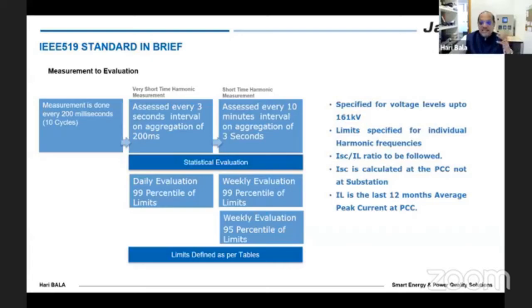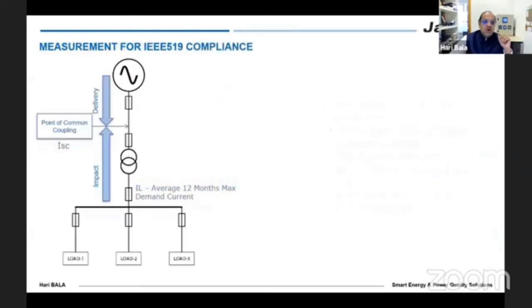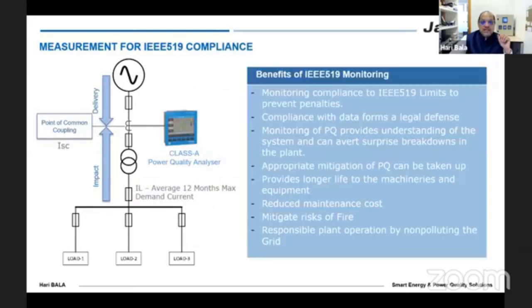IL is basically the last 12 months average peak current. I will also show you how these limits can help us. In short, at the point of common coupling, we need to determine our ISC and the 12-month average maximum demand current, and then we will have ISC by IL values, which will be compared onto the table. I will show you the table on the next slide.